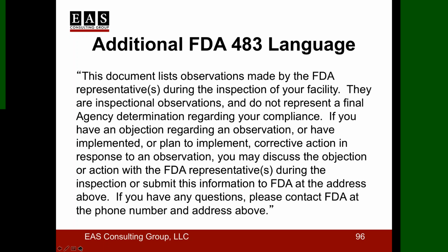So this document lists observations made by the FDA representatives during inspection of the facility. Their inspection observations do not represent a final agency determination regarding your compliance. Why that is important is because the FDA investigator is not like the EU notified body person. He or she is not a compliance officer. So therefore, they cannot state, are you good or bad, like the EU person does. They're like a cop. Here it is. Someone else is then the judge, i.e. the compliance person.